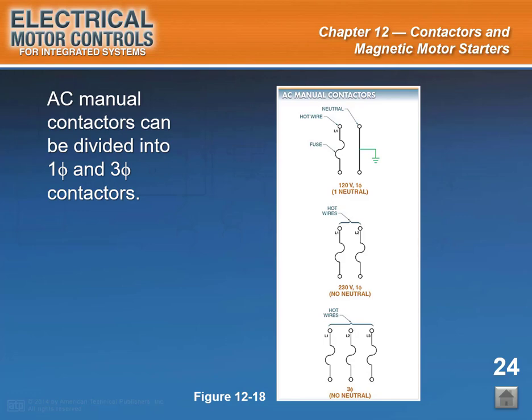Slide caption: AC manual contactors can be divided into single-phase and three-phase contactor types. See Figure 12-18. On single-phase systems, there are two hot wires and one neutral wire that is connected to ground at the service panel. A 120-volt, one-phase power source has one hot wire, the ungrounded conductor, and one neutral wire, the grounded conductor. A 230-volt, single-phase power source has two hot wires, L1 and L2, where both are hot and ungrounded conductors with no neutral.